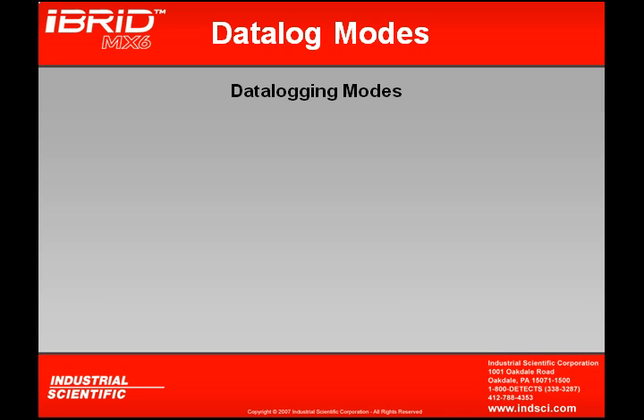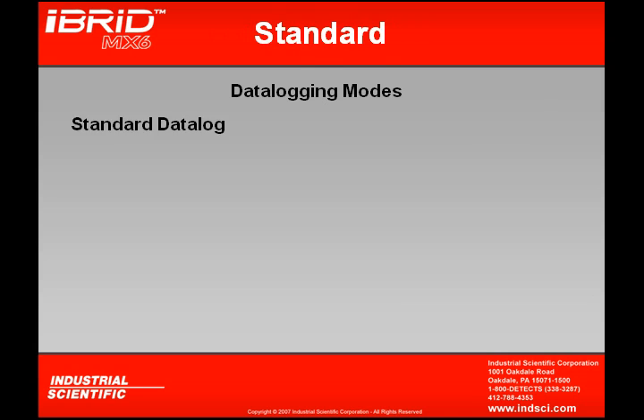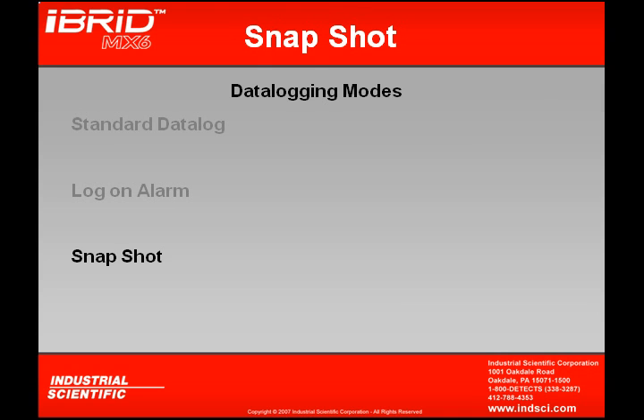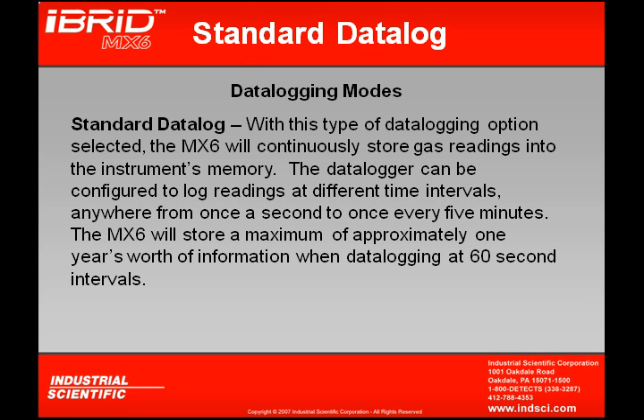Let's look at the different data logging modes available in the MX-6. We have Standard Data Log, Log on Alarm, and Snapshot. In standard data logging mode, the MX-6 will continuously store gas readings into the instrument's memory. The data logger can be configured to log readings at different time intervals anywhere from once a second all the way up to once every five minutes. The MX-6 will store a maximum of approximately one year's worth of information when the data logger is at 60-second intervals.